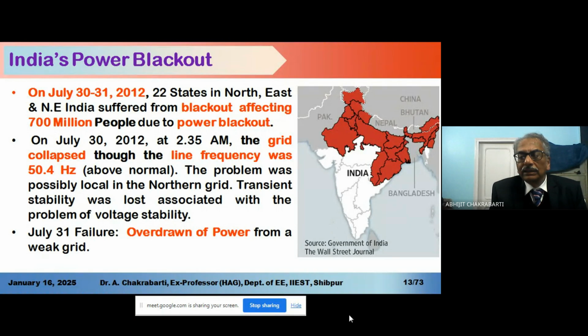Now, the southern grid was not affected, and the western grid was also not much affected. The reason was that the southern grid is mostly connected with the northern and eastern grid through HVDC lines, which saved the southern and western grids. The HVDC lines are fewer in number between the interconnection of northern, eastern and northeastern grids, so these grids suffered the most.